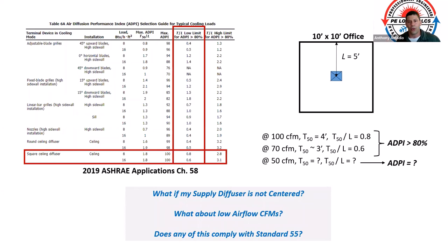What about low airflows? We can have low airflow rooms totally. When you have a room that's totally adiabatic — conditioned rooms above, beside, and below you — and it's just one person in a reading room, we're talking 30 to 50 CFM. It could be really small. How is this ADPI table going to help me predict comfort for an occupant? And we're going to see more.